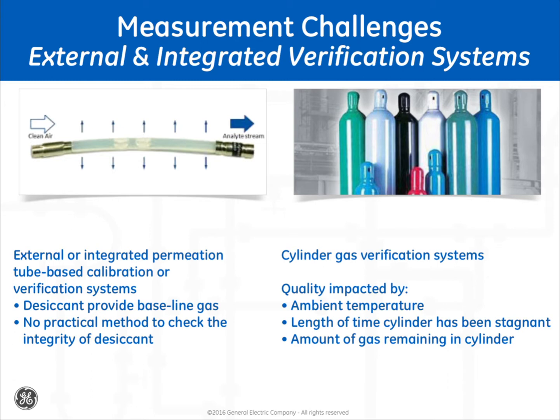Great care is needed when using calibration cylinders, even when these are properly prepared with known moisture contents, typically no lower than 1 ppm. The quality of the gas can be subject to the ambient temperature, the length of time the cylinder has been stagnant, and the amount of gas remaining in the cylinder.